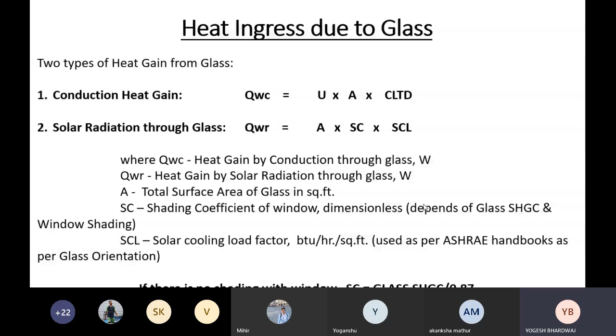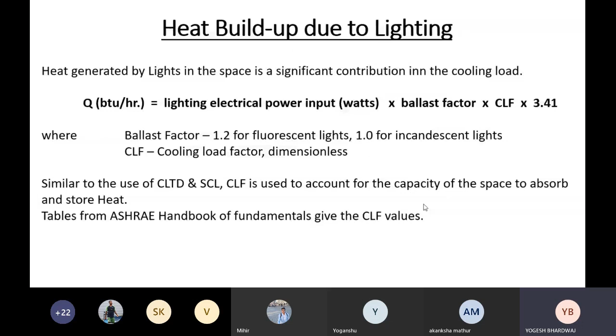Now heat buildup due to lighting. So if we have the lighting's load in watt, we can directly convert that into the heat generated from the lighting. So that is basically equal to the lighting input into ballast factor into CLF into 3.41. So ballast factor depends upon the type of fixture. 3.41 is basically a unit conversion of watt into BTU per hour. Then CLF is the factor which is actually, if your building is 24-hour operational, their CLF will be 1. So these values are given in ASHRAE guideline. So this equation, you will calculate the heat buildup from lightings.